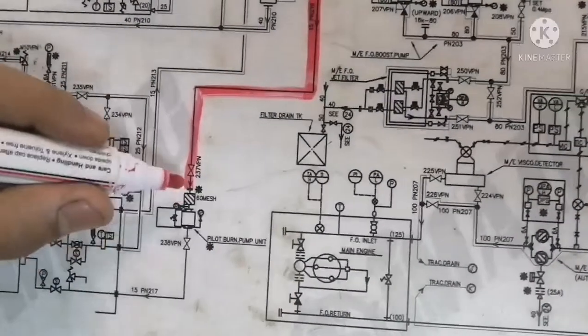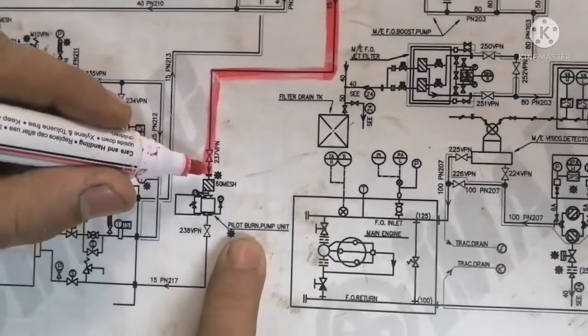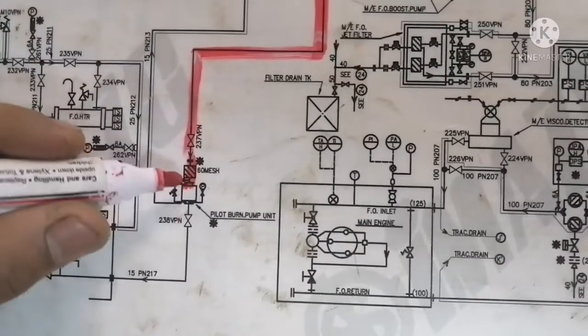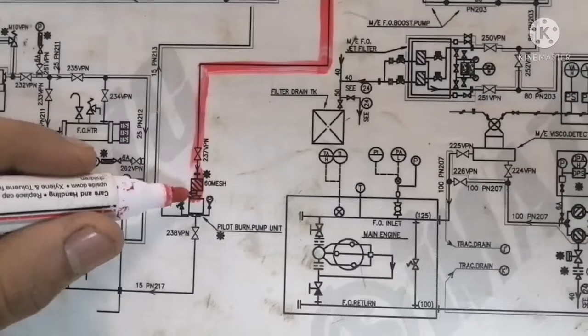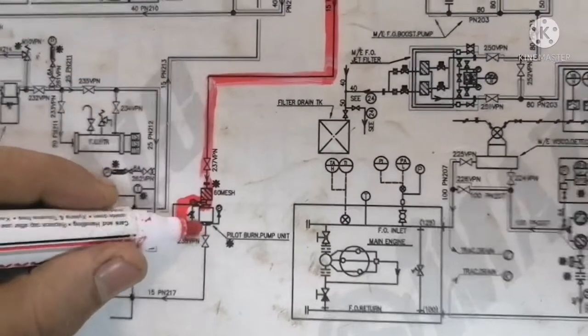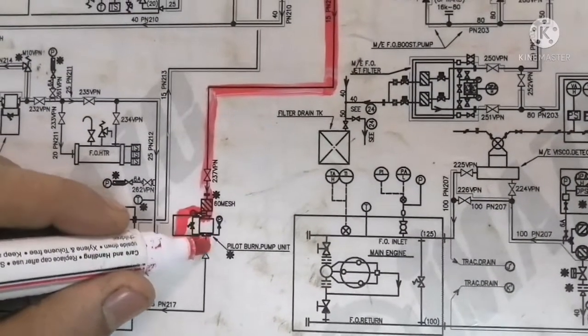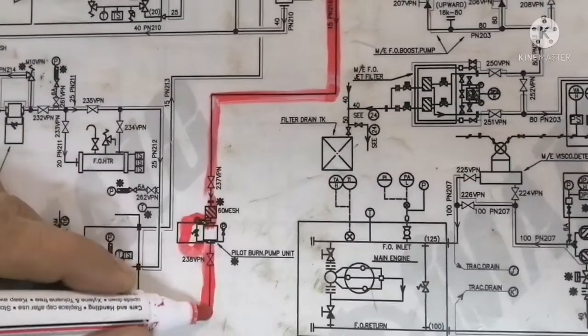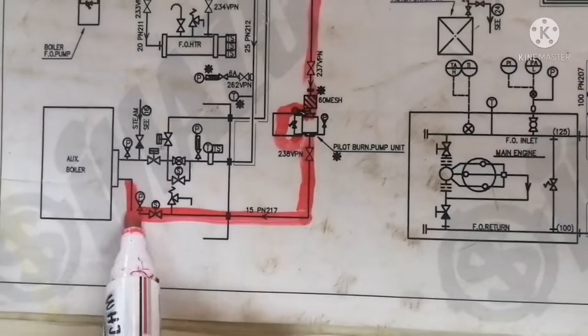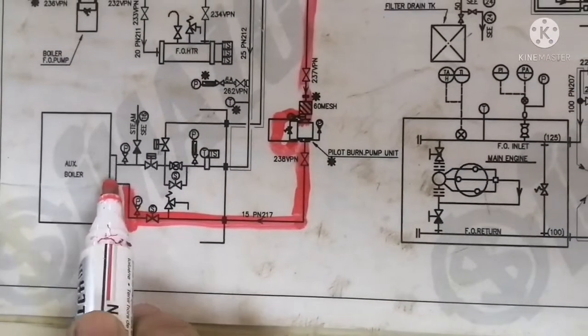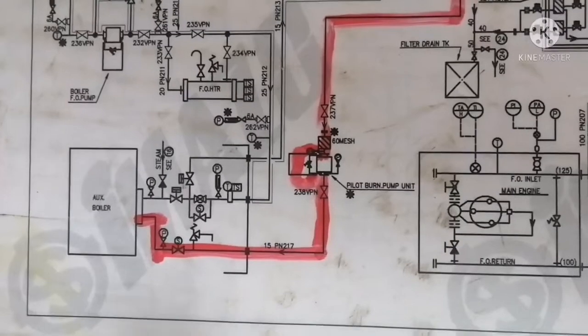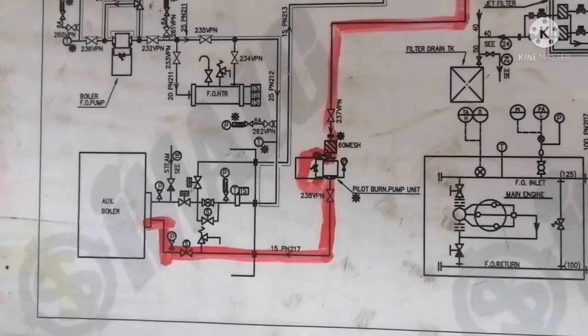This is your pilot burner pump. From the pilot burner pump, as I said, there will always be a relief oil line — it connects back to the suction line. The pump discharge will be going directly to your auxiliary boiler pilot burner.